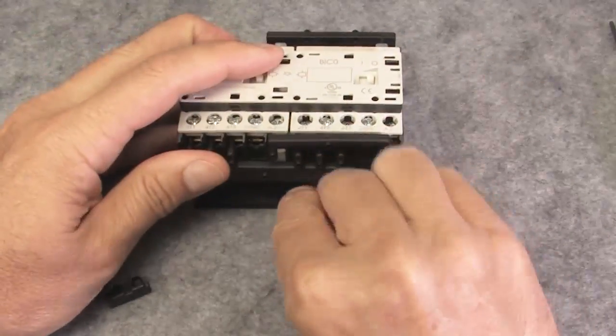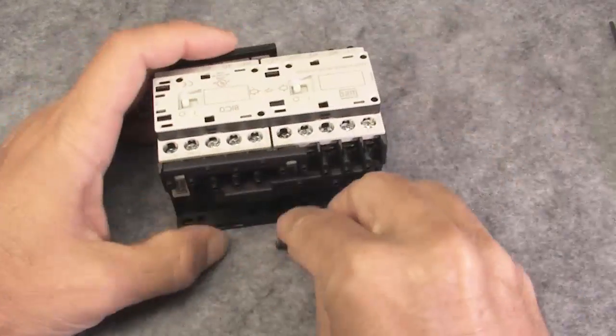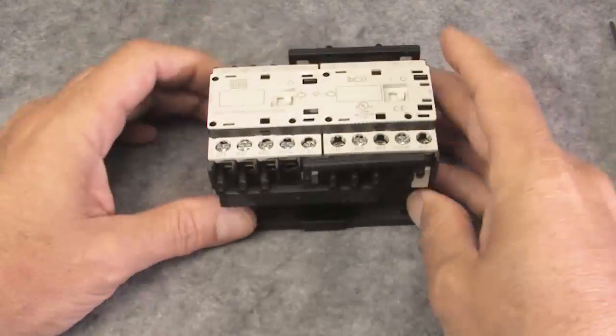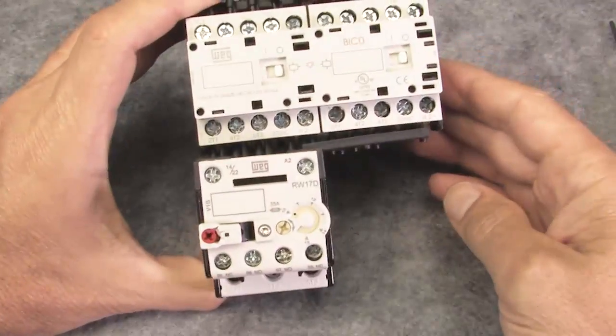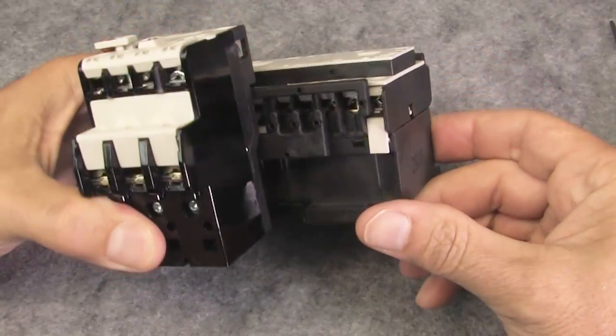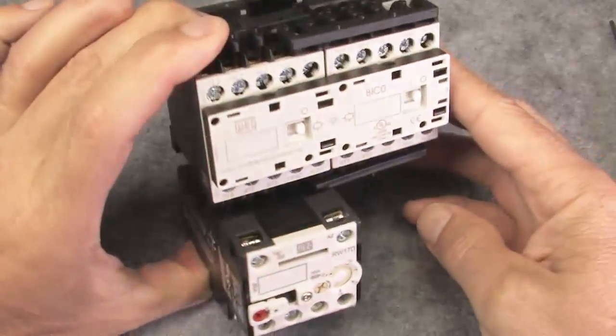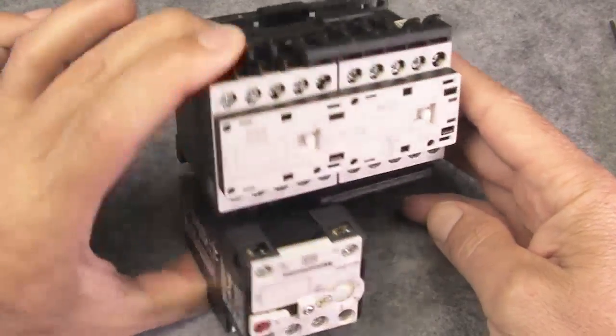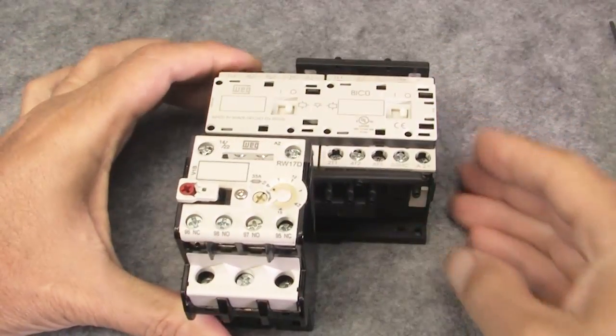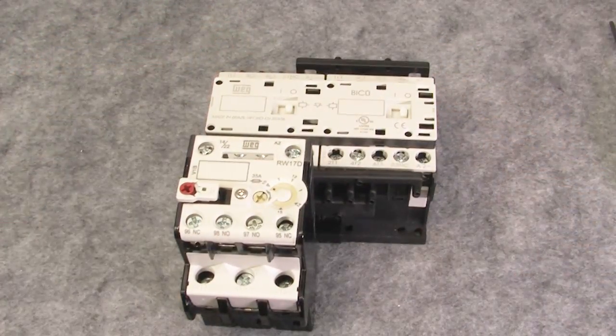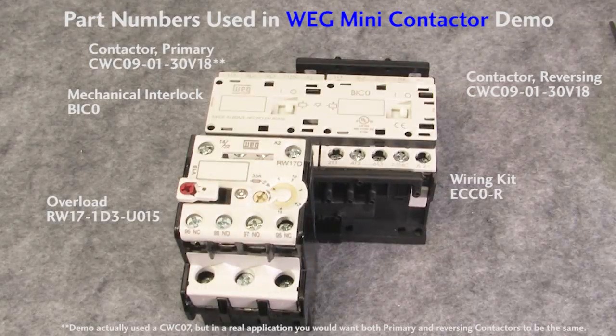If we put all of this together, don't forget the little tabs that lock the contactors together, they come with the interlock module, and add in an overload and look at this. We have a complete reversing motor starting solution with both mechanical and electrical interlocks all in one clean, easy to set up, inexpensive configuration for the 7, 9, 12 and 16 amp 3 pole WEG mini contactors. Awesome.